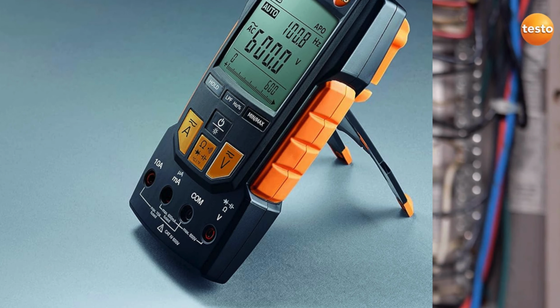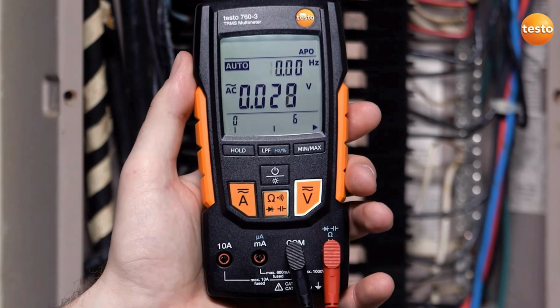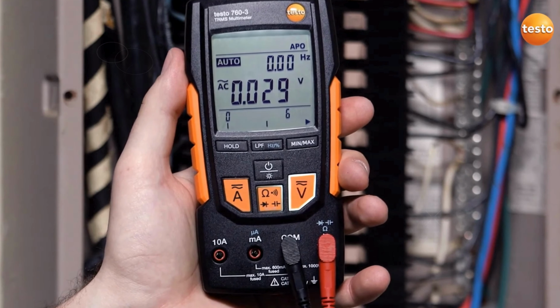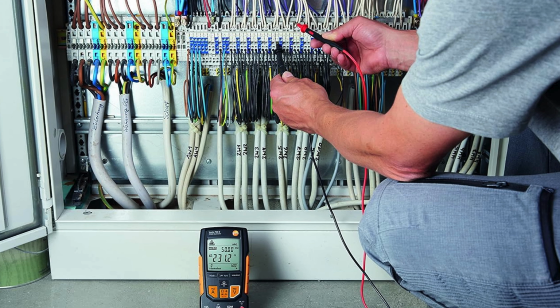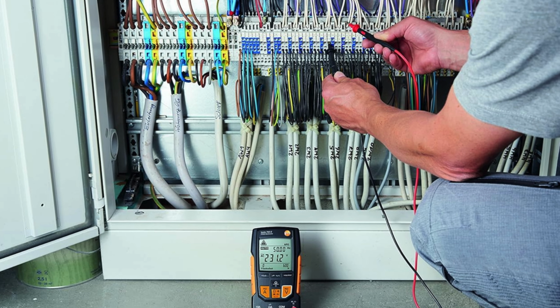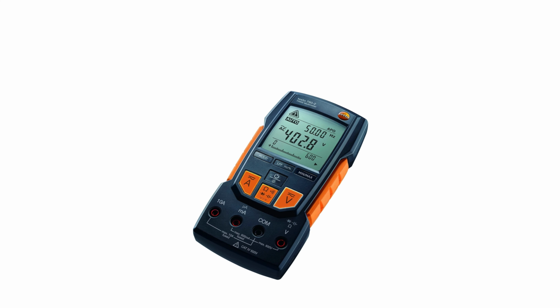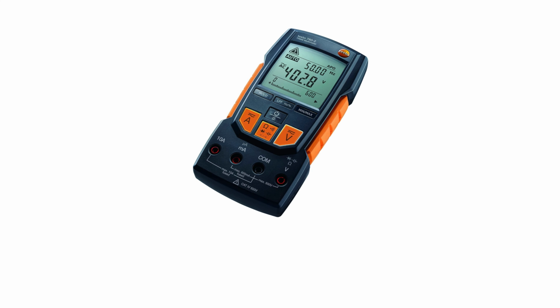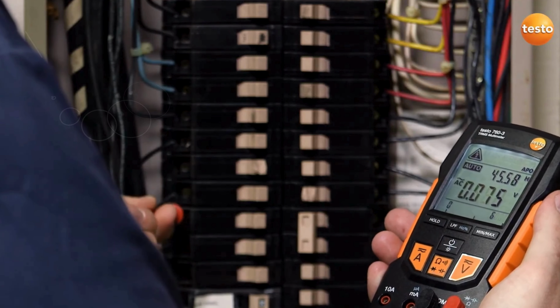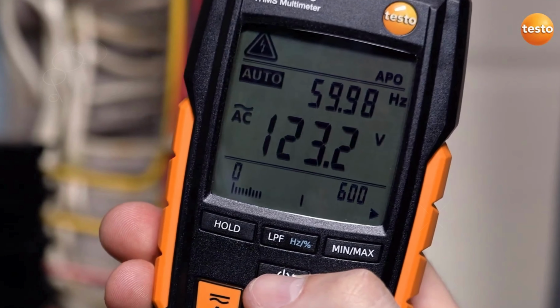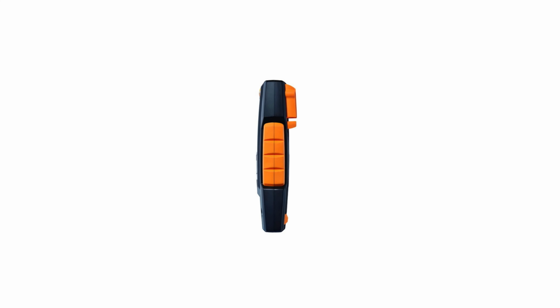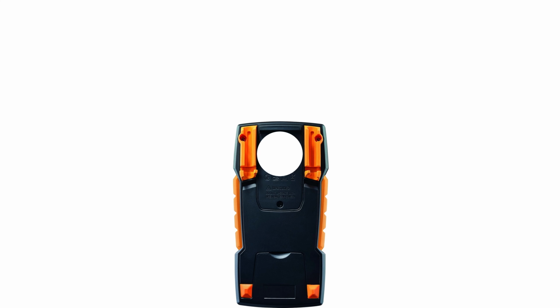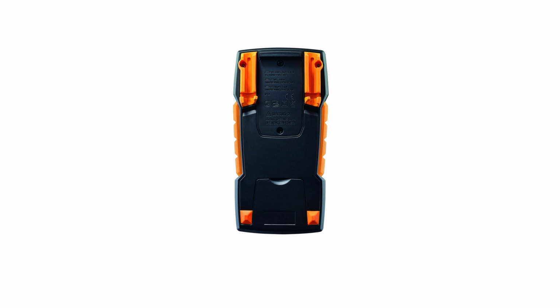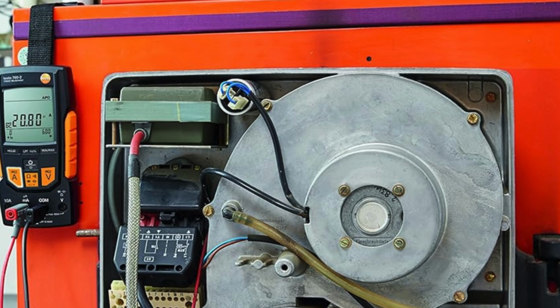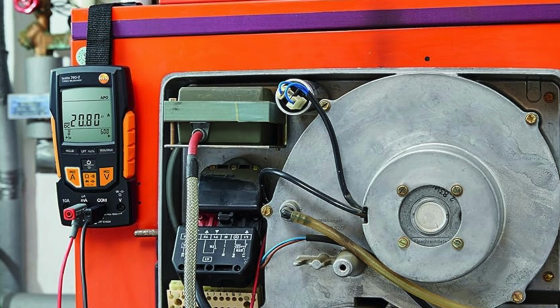What truly sets the Testo 760-2 apart is its intelligence. The built-in automation allows for quick adjustments, eliminating mistakes and optimizing accuracy while saving you valuable time in the field. The rugged housing and molded lead holder guarantee durability, making it perfect for tough working environments. Plus, the backlit display ensures visibility in all lighting conditions. The scope of delivery includes everything you need: the 760-2 voltage meter, test leads, 3 AAA batteries, a Type K thermocouple adapter, an instruction manual, a quick start guide, and a certificate of conformity. Whether you're a seasoned HVAC technician or just starting, the Testo 760-2 is undoubtedly one of the best HVAC multimeters on the market, designed to elevate your professional experience.